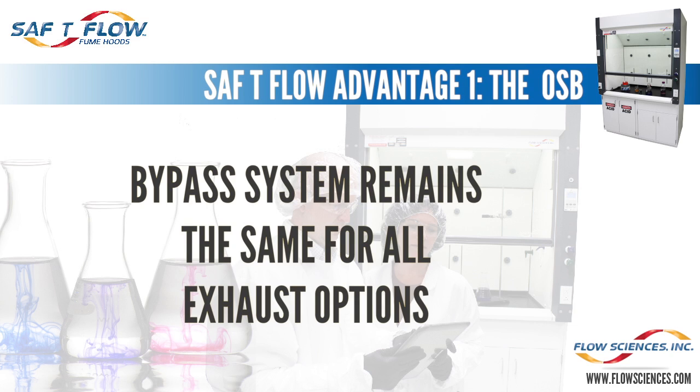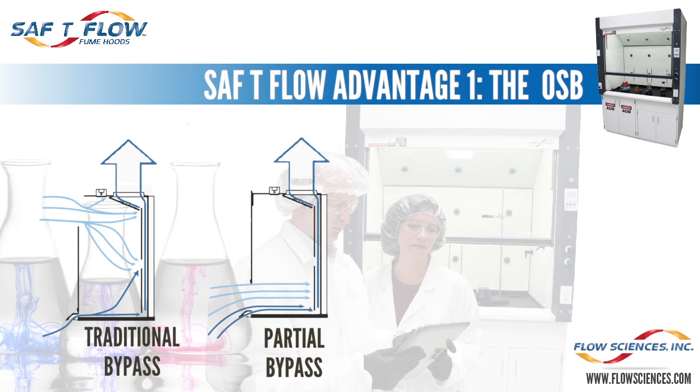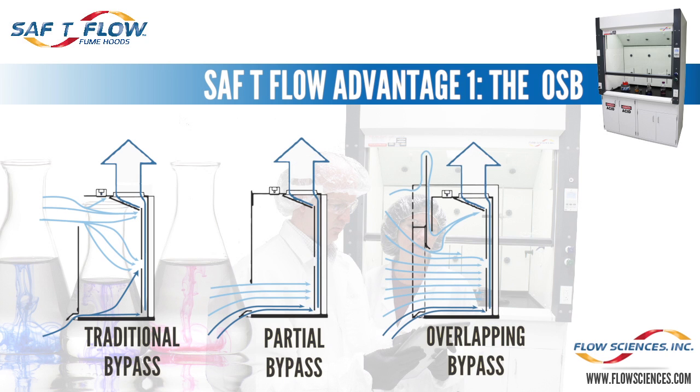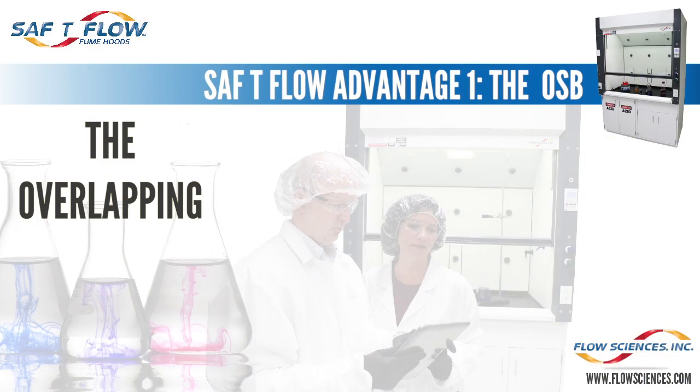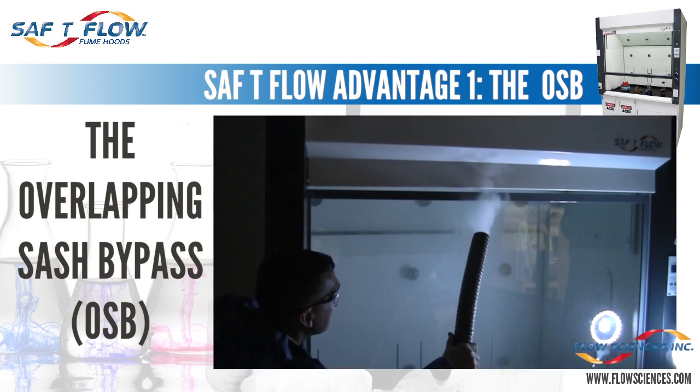At least eight significant advantages are offered in this brand new product, and we're going to focus on each and every one in this presentation. Advantage one: the Saf T Flow fume hood has a bypass system that never needs to be changed regardless of how a facility's exhaust strategy changes. Both the traditional and partial bypass require change-out or alteration if a building updates and reduces its fume hood exhaust strategy. The Saf T Flow fume hood uses a newer third bypass design called the Overlapping Sash Bypass, or OSB. The very same Saf T Flow fume hood is installed as a constant volume, low constant volume, or VAV hood.